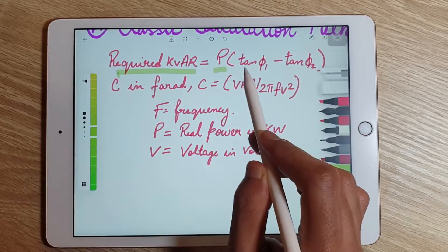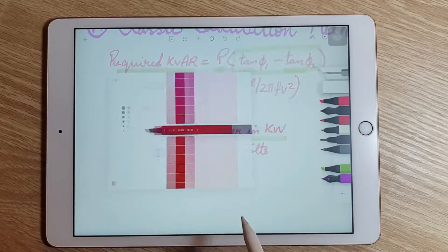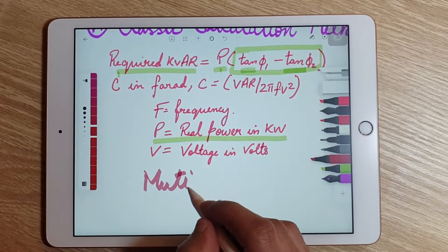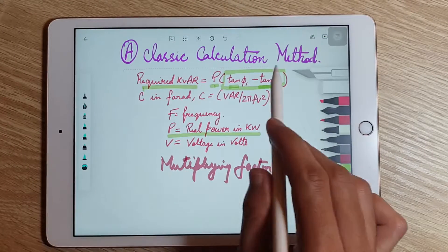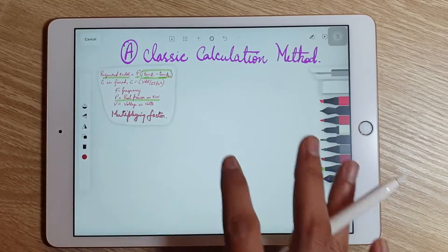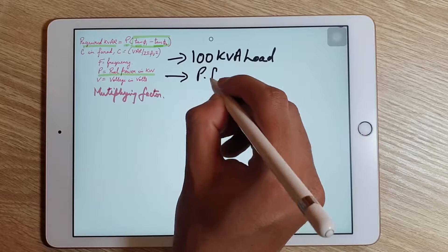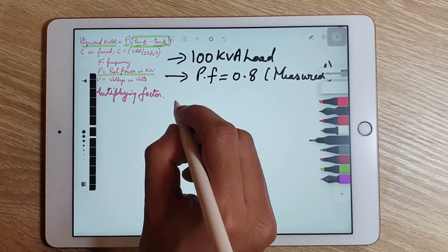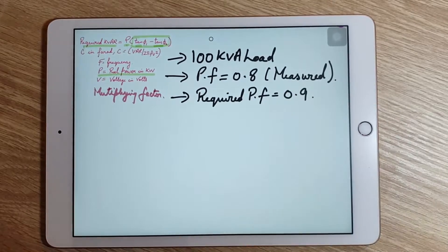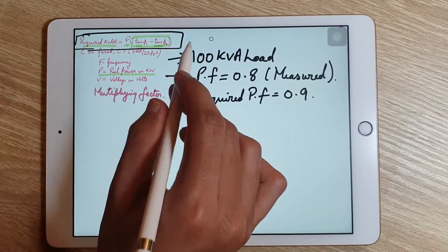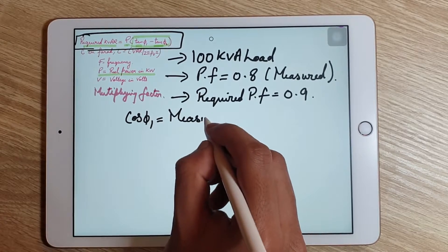P is the power in kilowatts, and (tan θ1 − tan θ2) is a multiplying factor which we calculate using the required power factor and the measured power factor of the system. Let's assume we have a load of 100 kVA with a measured power factor of 0.8, and the required power factor is 0.9, so we need to improve the power factor from 0.8 to 0.9 and require a certain amount of KVAR for this improvement.